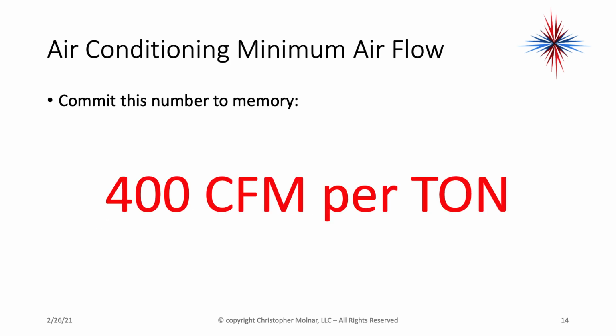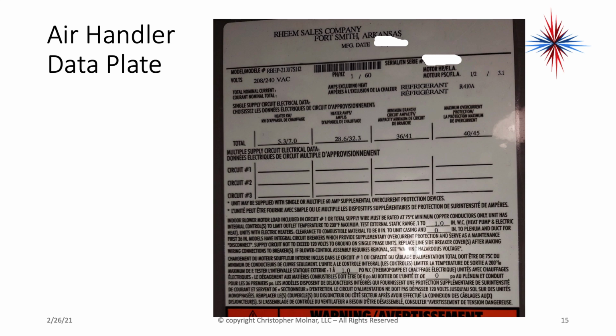So why does it all matter? You have to remember our magic number of airflow for air conditioning. We have to move 400 cubic feet per minute of air per ton of air conditioning. There's no option on this. This is the required airflow for air conditioning. So if we look at our air handler data plate, and I have whited some stuff out here just to protect people's privacy and make sure no one registers serial numbers that they shouldn't.